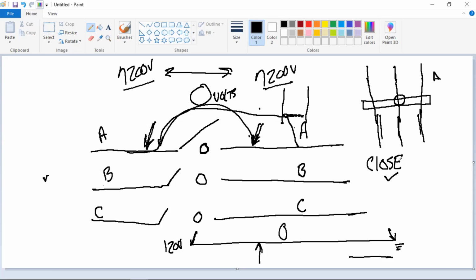Once again, it should have been done. 99% of the time it has been done, unless it's a real old switch location or something's happened on the circuit where you've had to change things around. And then the recommendation from the dispatcher and the supervisor will be, please go ahead and phase that switch before you close it. And that's the procedure to do it. Just put your Hastings fiberglass sticks across the open point right here, and your voltage reading should be 0.